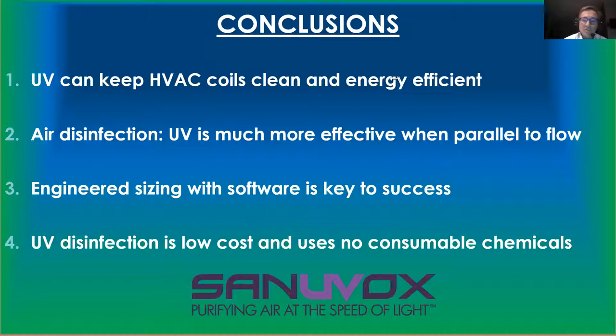On the lamp that we use, which is a bit bigger, mind you, not all manufacturers use the same lamp. We use a T6 format, which is 19 millimeter diameter. So the cross section is bigger, the current density is lower, and as a result, we guarantee them for 17,000 hours. Most of the industry use what they use in the water side. They use the T5 lamp. The T5 lamps are good in water because they're well cooled, but in air, they tend to overheat a little bit, and they don't last as long. Their density of current is higher, and their typical guaranteed life is 1 year. So you'll hear both 1 year or 2 years, but they're not the same type of lamps.